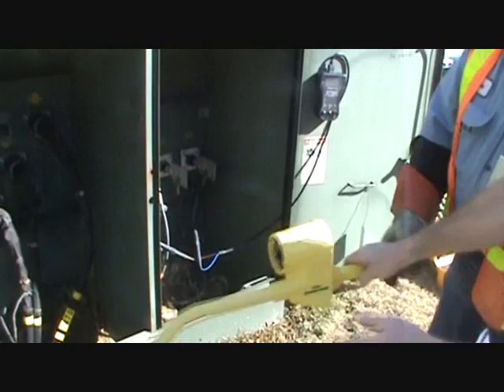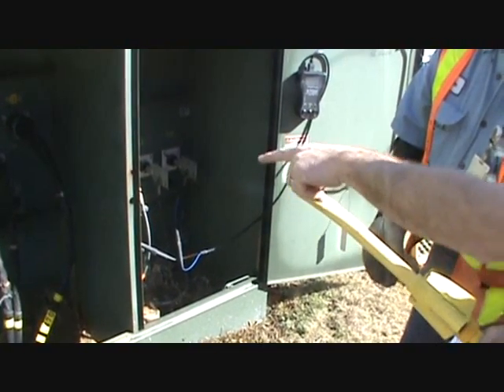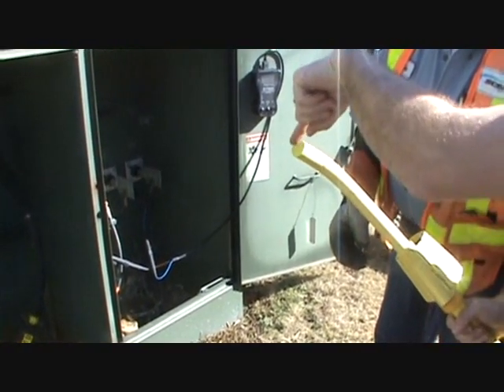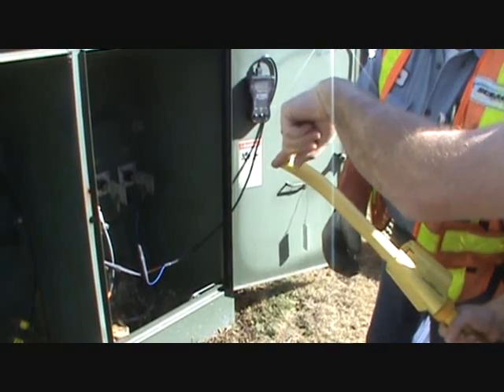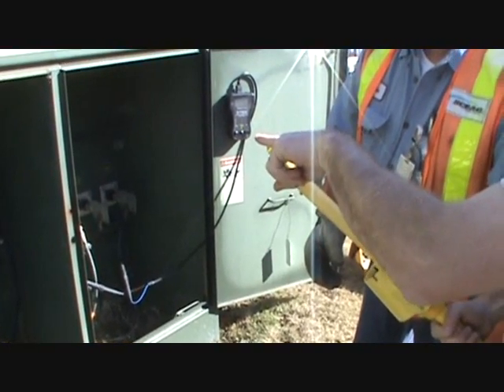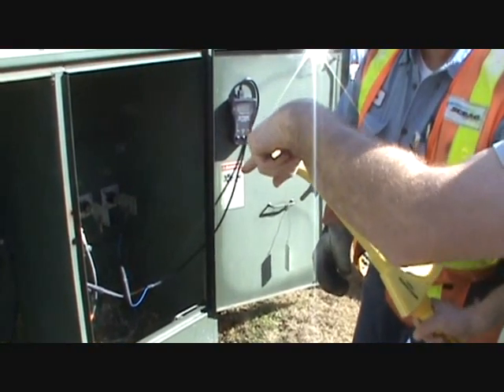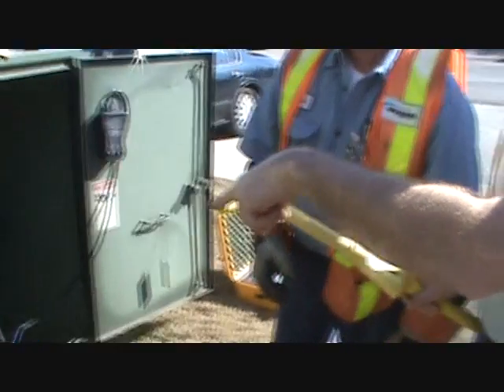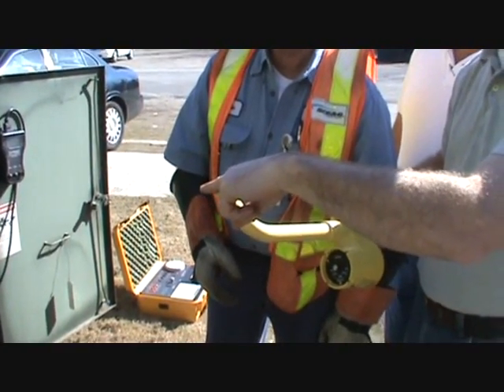There's a concave tip here, so when we're picking that up, we're going to go onto the neutral wire, and the cable should be perpendicular, laying in that concave tip. If the wire's like this, it won't pick it up, it has to be like this. Also, if you put it on the wire and it doesn't pick it up, rotate it 180 degrees and check it again.